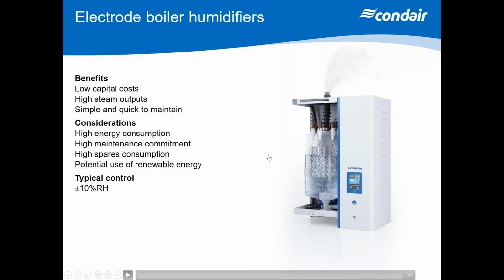As we go back to our electrode boiler, as we're producing steam, we have a concentration of minerals, and after a certain amount of time, this unit will say, I can't produce steam anymore, and at that point, the unit will alarm out, and you have to take the cylinder out and you throw it away and you buy a new one. And they're up to £500 to £600 now. Prices have increased to replace a cylinder. So they're not the cheapest thing to replace. So the big question is, how long is my cylinder going to last before I have to chuck it away and buy a new one?